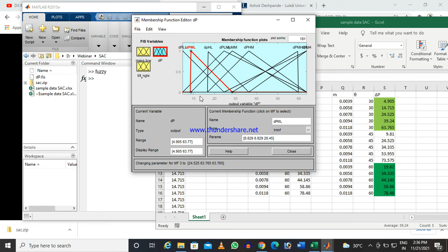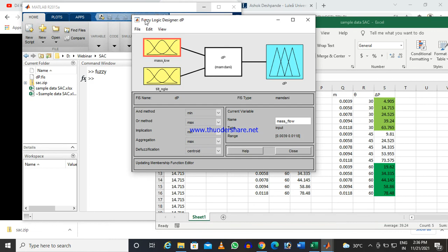Now I am coming to this medium flow. So this is my medium low flow, but that range will be, just 1 minute. So similarly, a total of 9 membership functions will come like that. This is a gross idea, so you have to implement all that, and after that you need to define the rule base. So you double click on that, and here you see these are the rule base. If mass flow is low and tilt angle is low, then the differential pressure will be low with low rate. Like that, a total of 9 rules I have defined here.